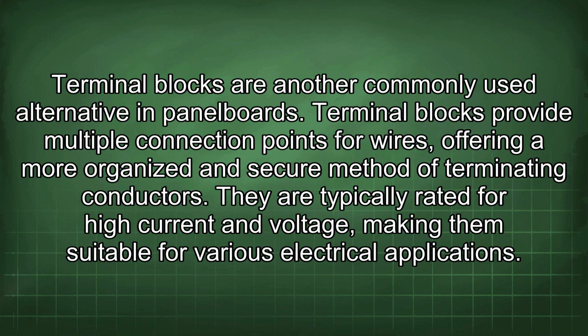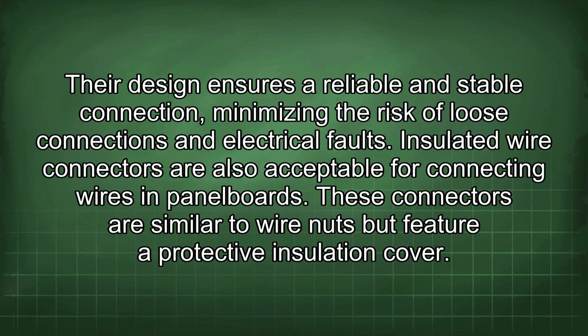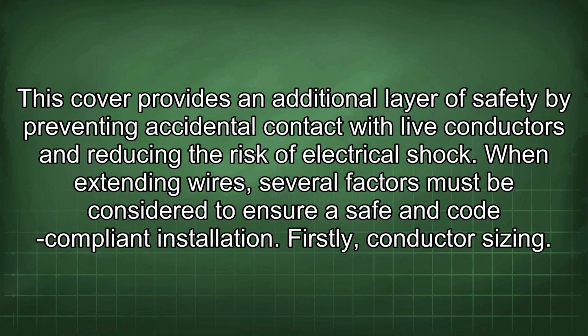Terminal blocks provide multiple connection points for wires, offering a more organized and secure method of terminating conductors. They are typically rated for high current and voltage, making them suitable for various electrical applications. Their design ensures a reliable and stable connection, minimizing the risk of loose connections and electrical faults. Insulated wire connectors are also acceptable for connecting wires in panel boards. These connectors are similar to wire nuts but feature a protective insulation cover. This cover provides an additional layer of safety by preventing accidental contact with live conductors and reducing the risk of electrical shock. When extending wires, several factors must be considered to ensure a safe and code-compliant installation.